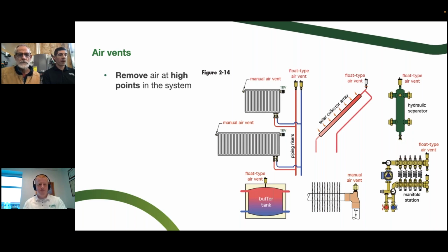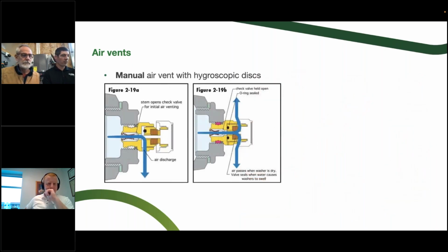So if you put a 1 by 1/8 inch tee on a straight line of pipe with the pump running, that's not really a great spot for that. You're going to be moving too fast. You're not going to have enough space up there to collect a lot of air. So the air vents are going to be better at a high point to catch something that might get stuck in a heat exchanger, as an example. So let's look at a couple different versions of this, and if you want, I can narrate that, and I'll turn on the shop cam over here somewhere.